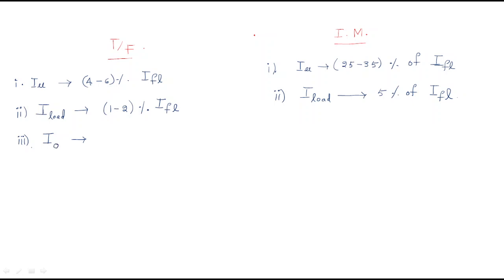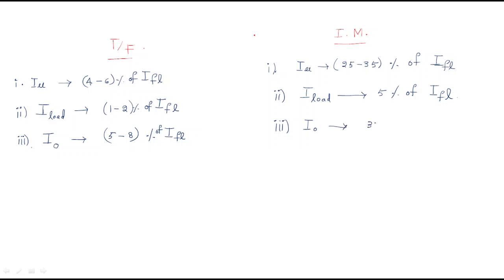The no-load current of the transformer is 5 to 8% of the full load current. In the induction motor, the no-load current is 30 to 40% of the full load current. Every time, the no-load current and full load current of the induction motor are higher than those of the transformer.